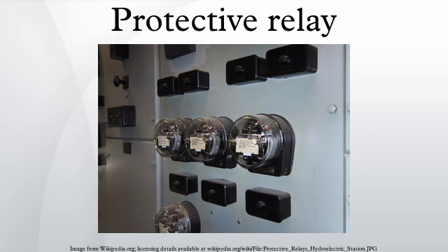Static application of electronic amplifiers to protective relays was described as early as 1928, using vacuum tube amplifiers. Devices using electron tubes were studied but never applied as commercial products, because of the limitations of vacuum tube amplifiers. A relatively large standby current is required to maintain the tube filament temperature. Inconvenient high voltages are required for the circuits, and vacuum tube amplifiers had difficulty with incorrect operation due to noise disturbances.